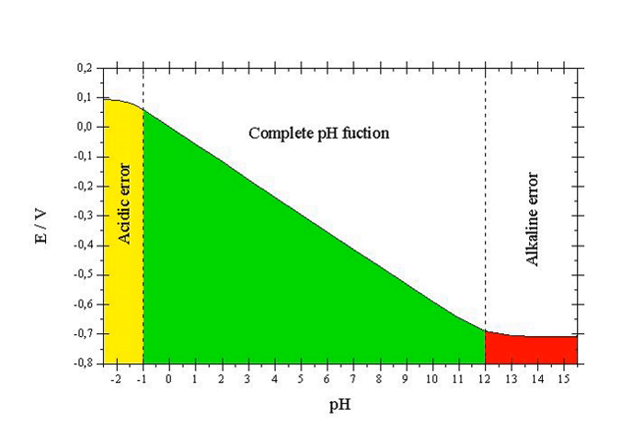A glass electrode is a type of ion-selective electrode made of a doped glass membrane that is sensitive to a specific ion. The most common application of ion-selective glass electrodes is for the measurement of pH. The pH electrode is an example of a glass electrode that is sensitive to hydrogen ions. Glass electrodes play an important part in the instrumentation for chemical analysis and physicochemical studies. The voltage of the glass electrode, relative to some reference value, is sensitive to changes in the activity of certain types of ions.